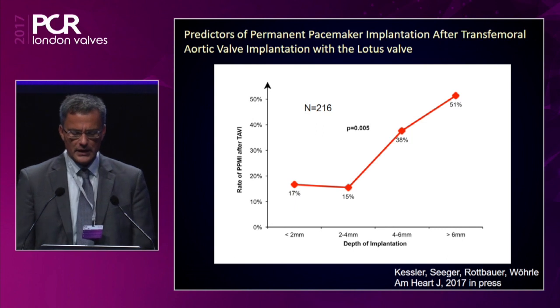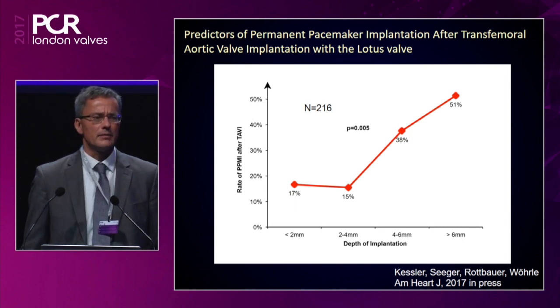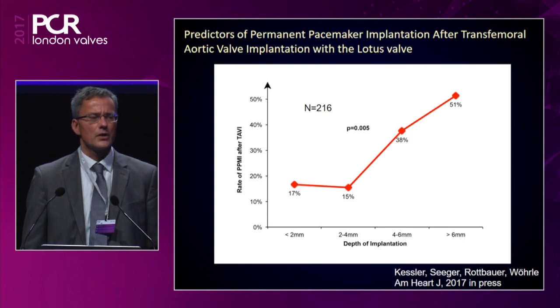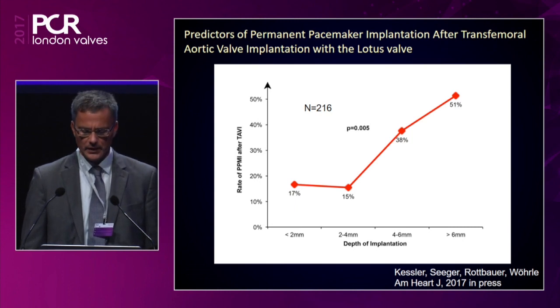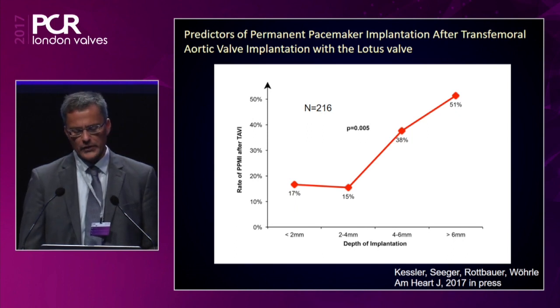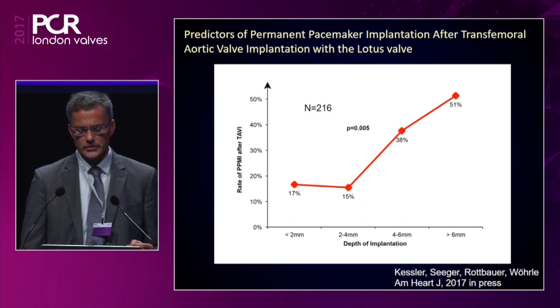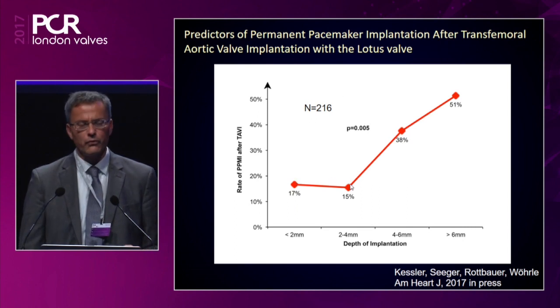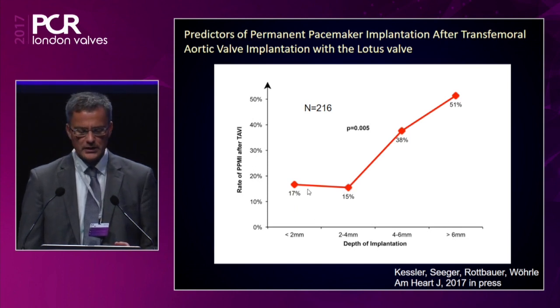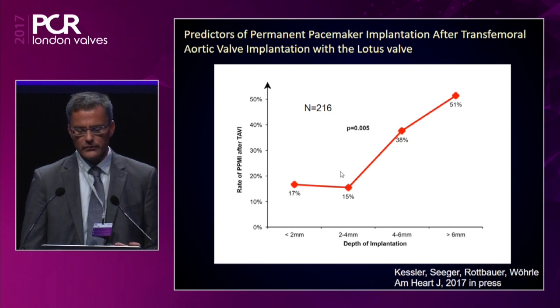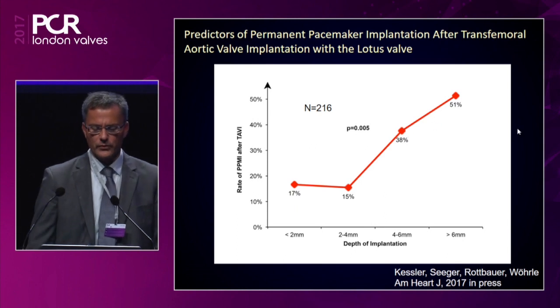So these are again data from Ulm, based on 216 patients with a Lotus valve implantation without a previous permanent pacemaker. And they see that the implantation depth is very important. If we placed the Lotus valve in the range of 0 to 4 millimeters below the aortic annulus, we had a pacemaker rate of 15 and 17%. But if we had to implant it deeper, for example, because we had a small distance to the coronary ostia, you see that there was a significant correlation and an increase in the need for pacemaker implantation.